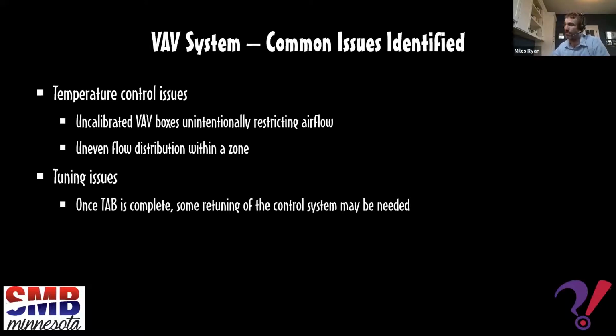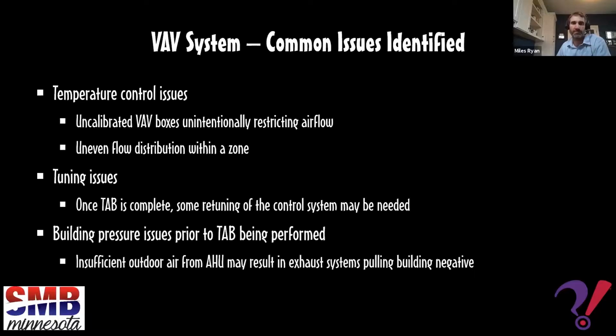And then when they were brought in December, they found a bunch of obstructions in the ductwork that resulted in a giant increase in flow from the makeup air unit. They had adjusted some things on the hydronic side, which changed a lot of the pressure characteristics of the hydronic system. And really, it threw off all of the tuning of those control loops that the temperature controls contractor had spent so much time in the previous months doing, and you had to come back and redo a lot of that work. So bringing the TAB contractor in far too late in this case really created a bunch of fruitless efforts on his part up until that point.